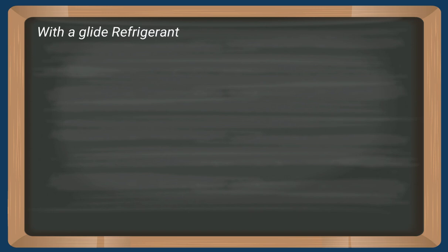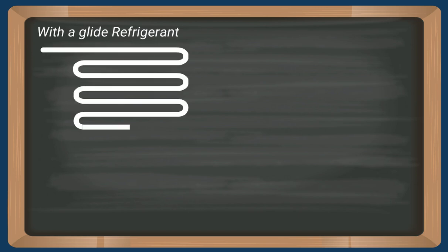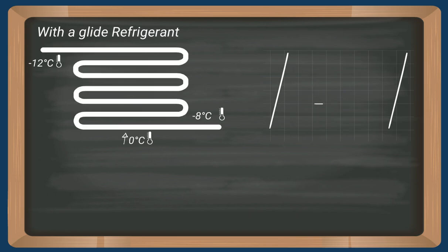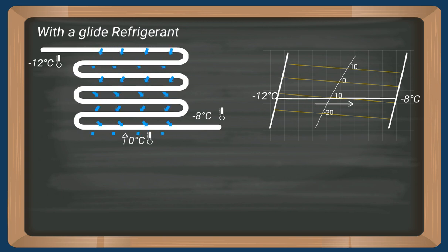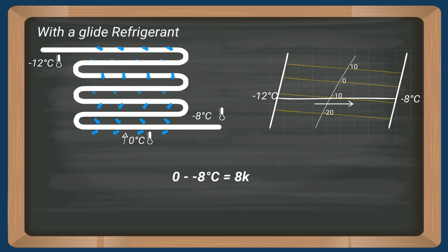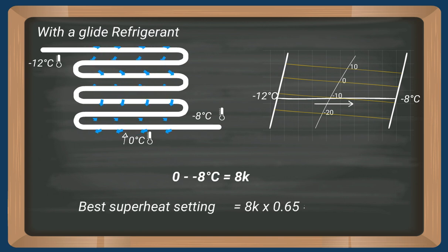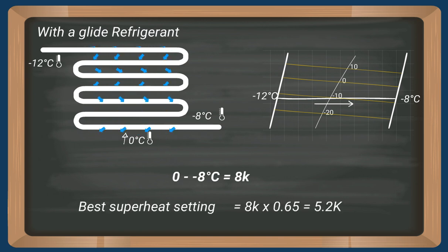The same applies to glide or zeotropic refrigerants. It's just that the mean temperature will be different. In this case, we're talking 8 degrees Celsius. So the superheat should be 5.2 Kelvin.